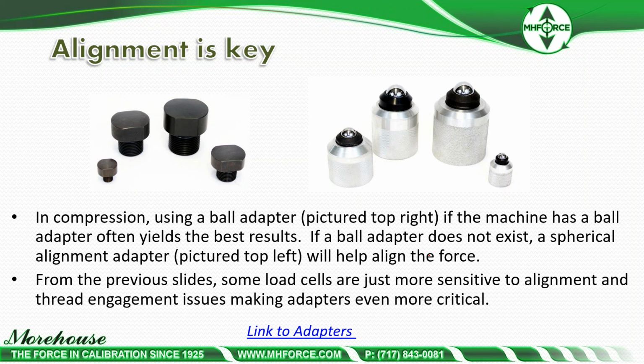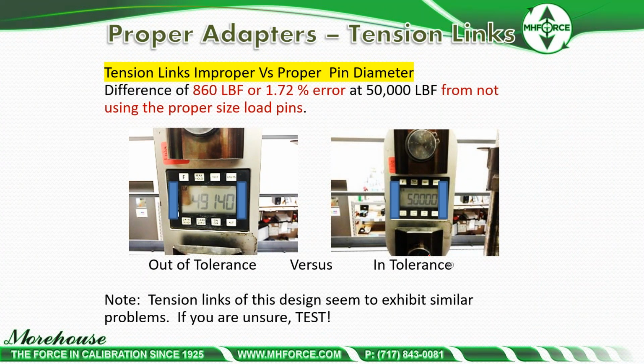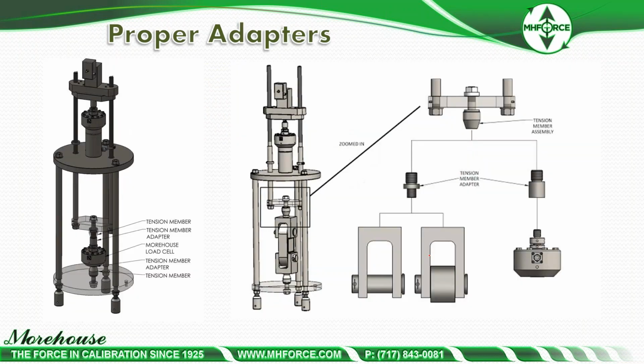From the previous slide, some load cells are just more sensitive. Yeah, we have load cells that are more sensitive to alignment than others. So I showed you that tension link. Here's one that we get a lot. Tension links, improper versus proper pin diameter. This device is spec'd at 0.1% of full scale. Difference of 860 pounds shown here, or 1.72% error at 50,000 pounds from not using the proper size load pin. If you don't know, test it. You can take two different pin sizes and test it. Just make sure they're both safe to go to that capacity.